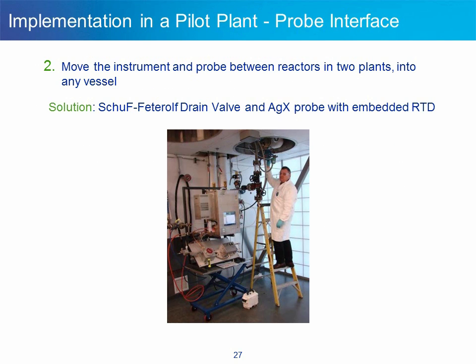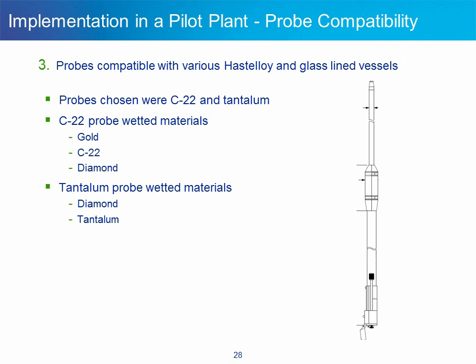Requirement number two — operators must be able to move the instrument and probe between reactors in two plants and insert the probe into any vessel chosen for a pilot study — was met using a SchuF-Feterolf drain valve and silver halide probe with embedded RTD. Requirement three — probes compatible with various Hastelloy and glass-lined vessels — was addressed by choosing C22 and Tantalum probes. On the C22 probe, the wetted materials are gold, C22, and diamond, allowing access to a wide range of chemical systems especially in Hastelloy reactors. On the Tantalum probe, the wetted materials are gold, diamond, and Tantalum, used extensively in glass-lined reactors.